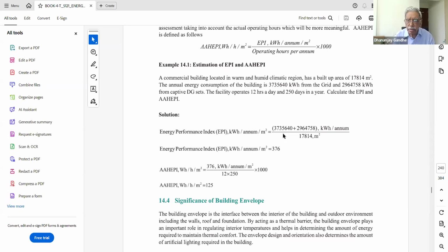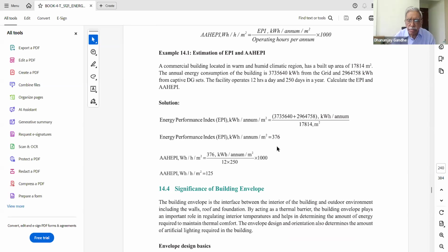Okay, so this is the value, and the average annual hourly energy performance index will be this EPI 376 divided by the number of operating hours. It is mentioned in the example that the facility operates for 12 hours a day and 250 days in any year. So 376 divided by 12 multiplied by 250, and it is to be multiplied by 1000. Don't forget that. And the answer that you get is 125. So average annual hourly EPI is 125.